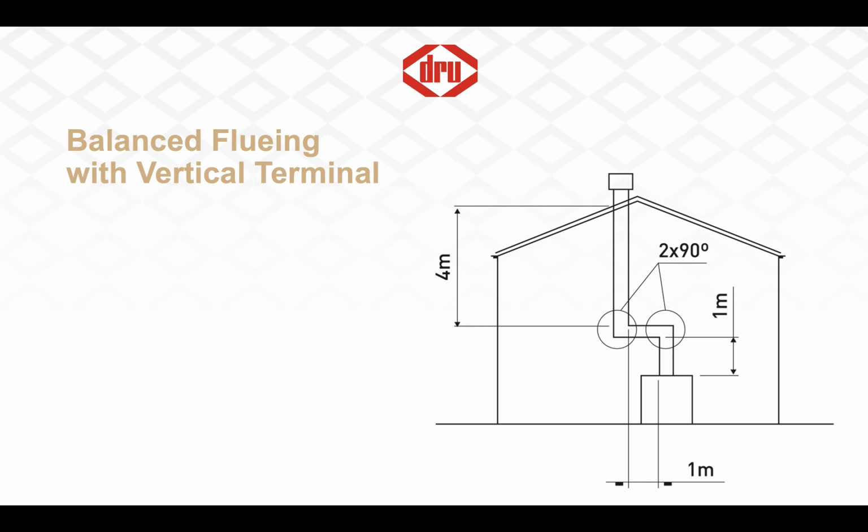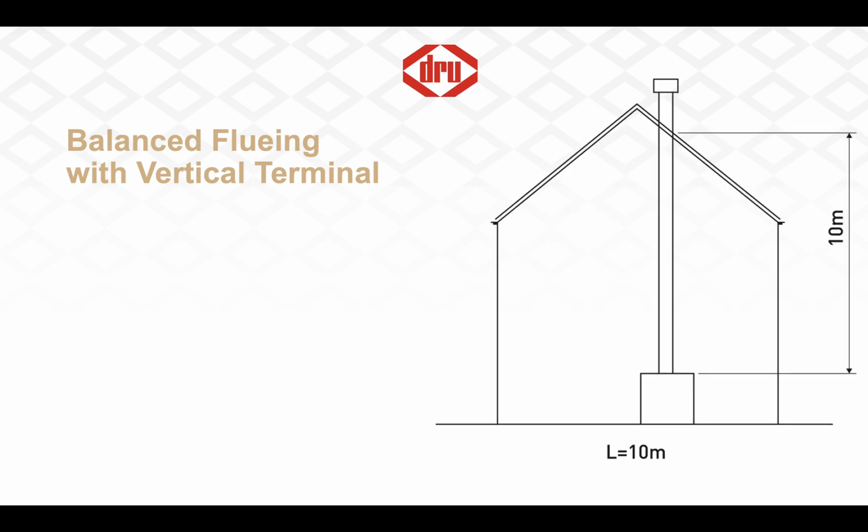Again, the overall flue length, number of bends, and particularly the maximum horizontal flue length are determined in each individual manufacturer's installation instructions. This dimension can often pose challenges, depending on the positioning of the appliance. Flue gases will naturally travel vertically, so requiring them to navigate multiple bends and horizontal runs will affect the operation of the appliance. Manufacturers' fluing systems and materials, as specified in their installation instructions, must also have EC approval.